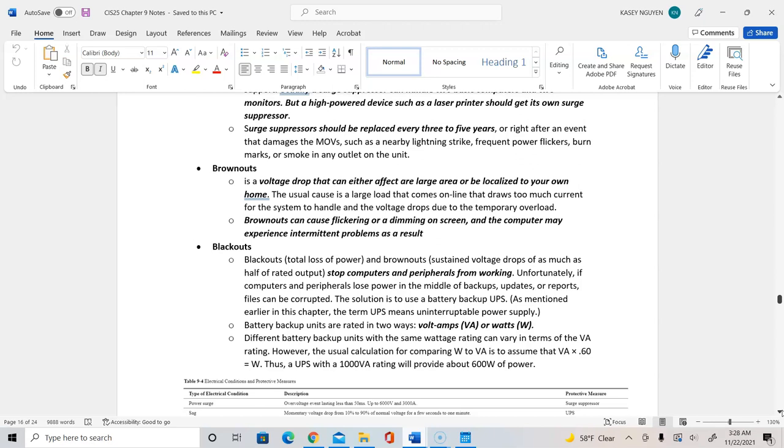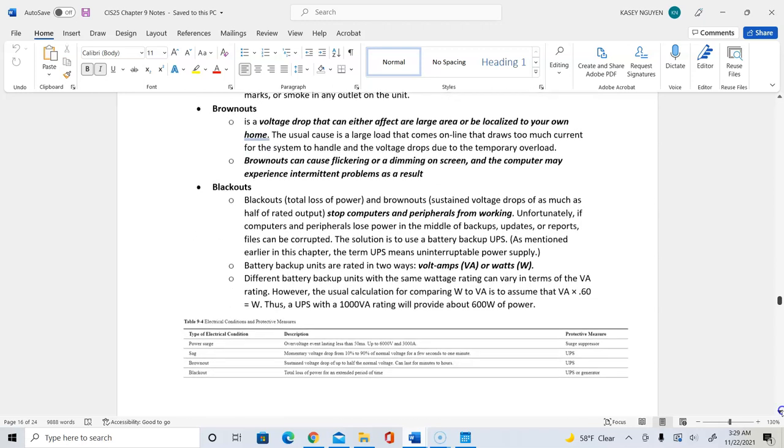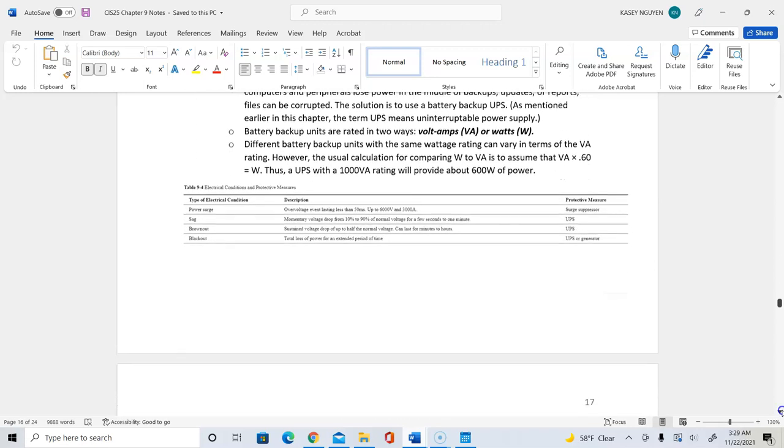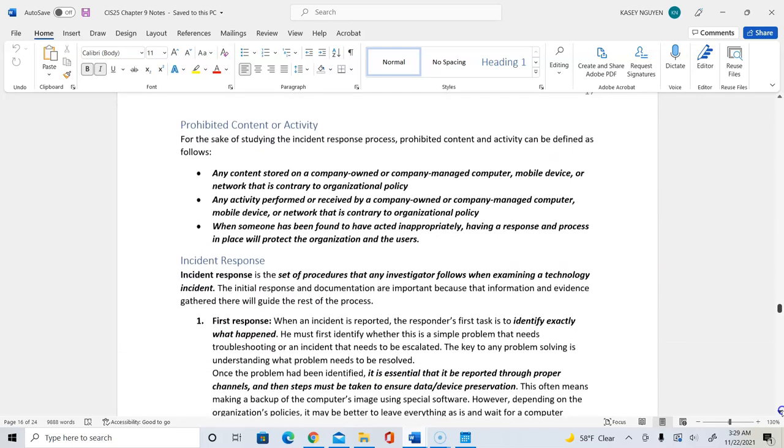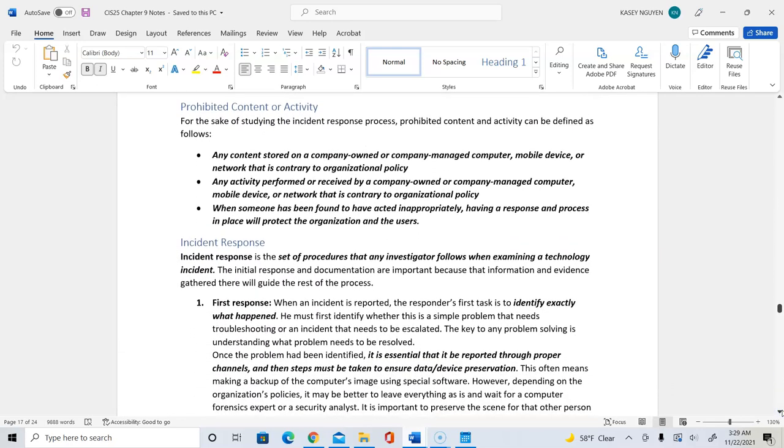In order to really identify the right surge protector, we would combine the wattage or the volt amp readings of the device and we would calculate and compare that to the maximum of the surge protector that can handle. And surge protector should be replaced between three to five years in that the MOVs would be deteriorating. And also in the case where we have lightning strike, frequent power flickers, burn marks, smokes, and so on, that cause damage to the surge protector. So we would then need to replace that. Brownouts and blackouts: brownouts is the voltage drop in that it would affect a large area that would be close to your home or your business. Blackouts would be that it is a total loss of power where brownouts is a sustained voltage drop into half of the output.